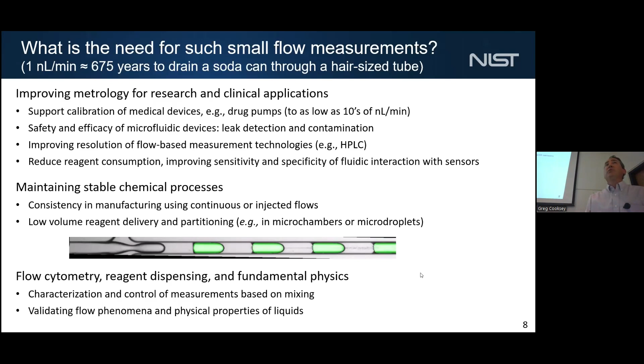So conventional technologies for measuring flow, I'm going to move through this pretty quickly. All of the National Metrology Institutes maintain the calibration of flow based on a very sensitive bucket and stopwatch. So you've got a microbalance and a timer, and you are measuring the accumulation of mass very precisely by thinking carefully about adjusted buoyancies and stick-slip interactions with micropipettes interfacing with those weigh pans, as well as evaporation and other physical forces that start to dominate on that scale.